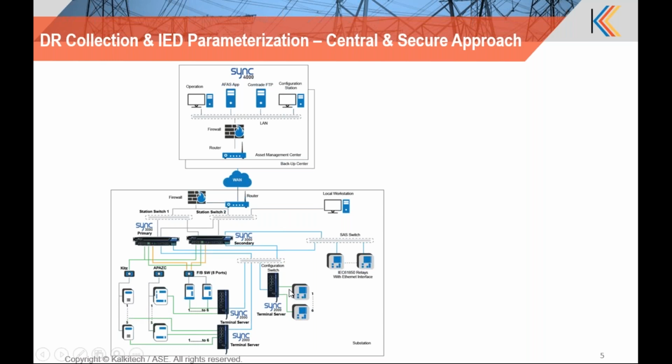But all these IEDs are connected to a redundant protocol gateway or data concentrator, which is used to collect the live data from all the IEDs plus the disturbance records from all the IEDs in their protocols. So this gateway should support all the protocols that are available in the substation, supporting multi-vendor protocols for the data collection as well as the disturbance collection scenario.